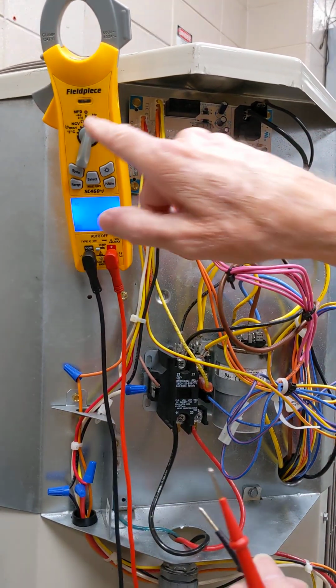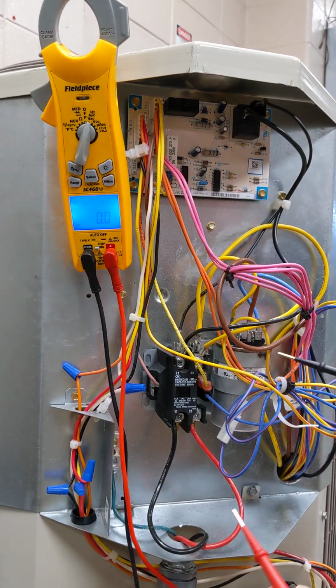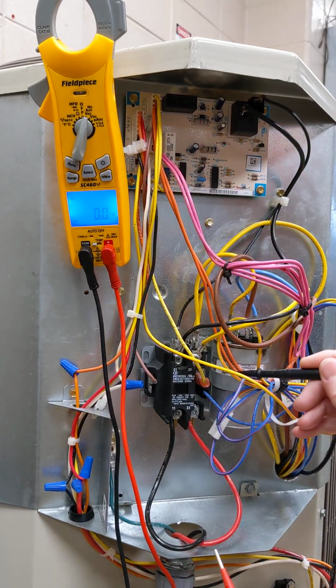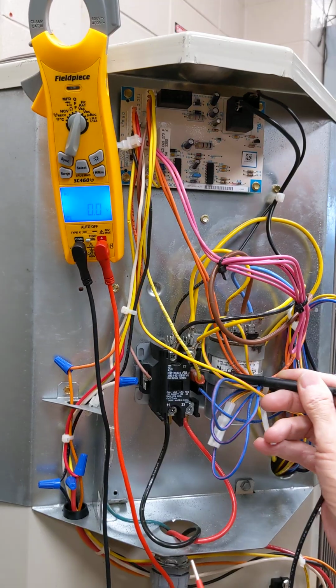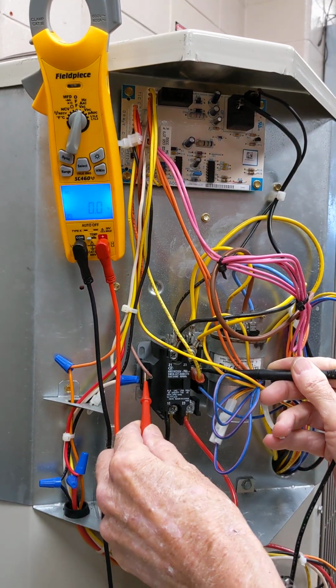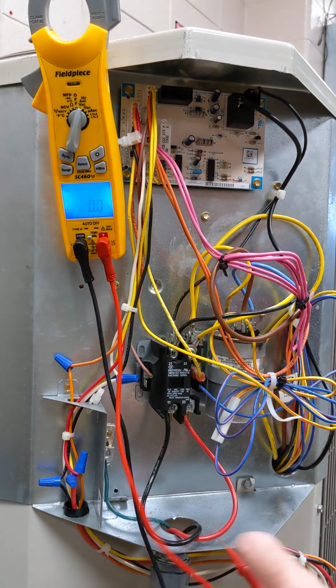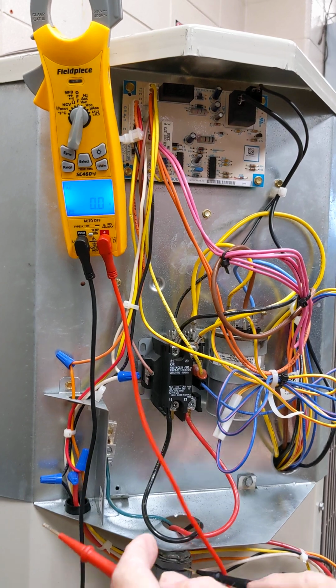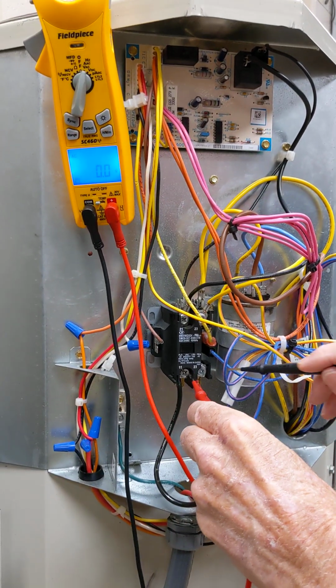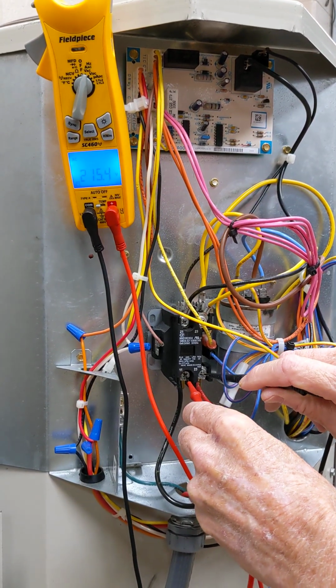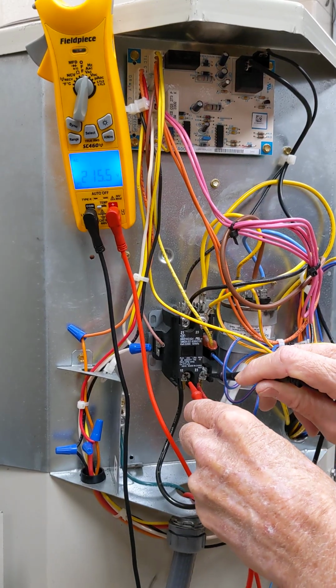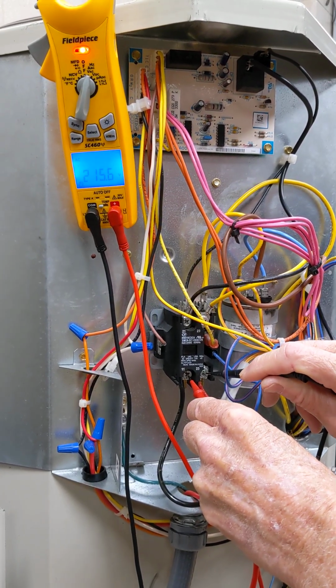How do I know? I set the meter to volts. I come here to my low voltage stuff and get on there and I have nothing. I come in where my whip is coming up to the high voltage, get on there, and I got power. So guess what? I'm going to pull the disconnect.